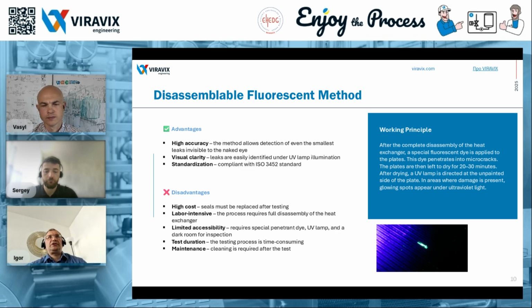Indeed, some companies have historically used the fluorescent method, specifically the disassemblable version, as their standard. This approach is justified when each test is intended to provide precise leak detection. In other words, when the goal is not just to confirm the presence of a leak, but to determine its exact location and nature. However, I wouldn't say this approach is justified in all cases because, as mentioned earlier, it is often more effective to first perform an integrity test without disassembly, using a more gentle method, and only if a leak is confirmed, proceed to locate it and determine its characteristics.